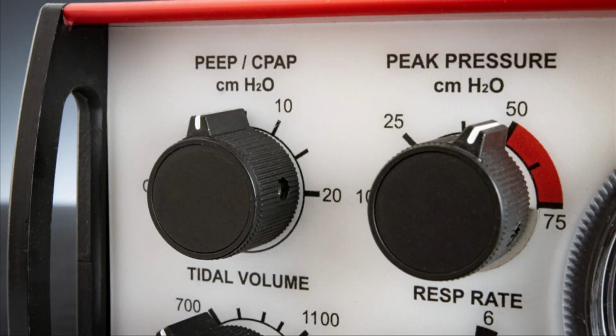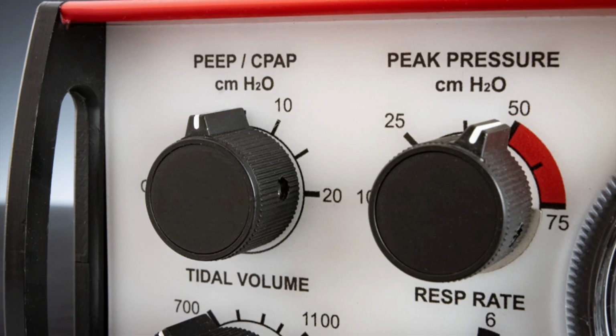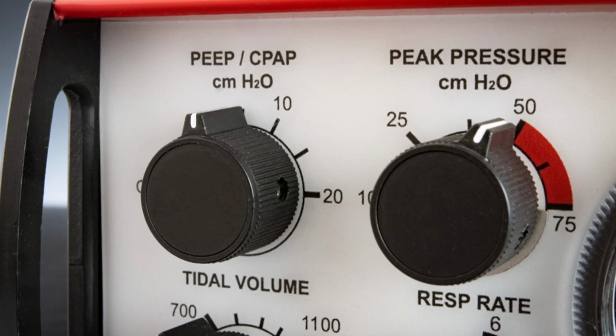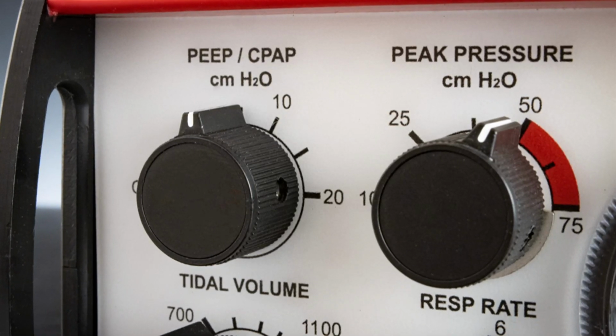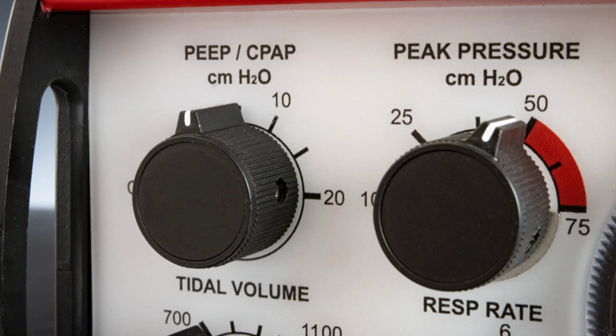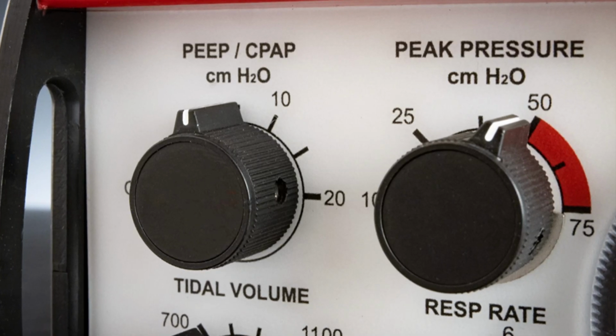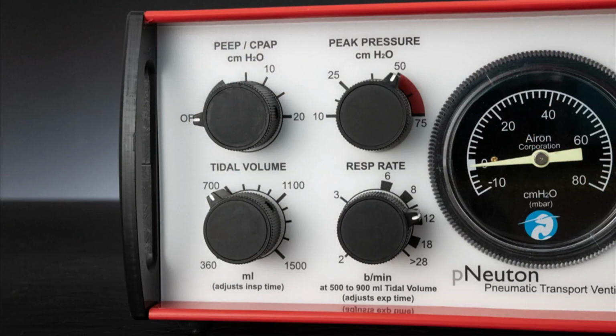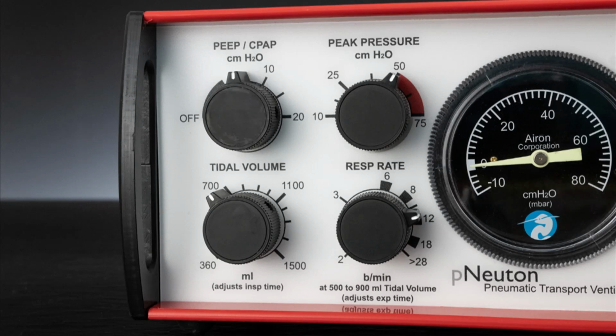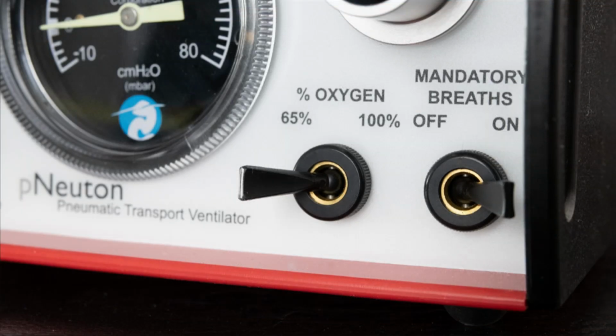Let's start at the top left with the control that provides both PEEP and CPAP. When the device is set for ventilation mode, PEEP will provide the baseline pressure. When not in ventilation mode, it supports CPAP for spontaneous breathing. The PEEP CPAP control adjusts up to 20 centimeters of water pressure. It has automatic sensitivity for changing patient needs with a maximum flow rate provided up to 140 liters per minute. The patient receives the FiO2 set by the percent oxygen control.